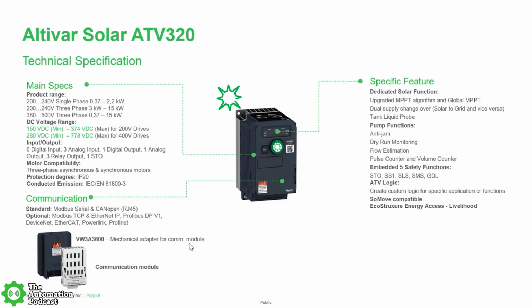Another cool thing that we have on the Altivar 320 Solar is that we also have integration into the Schneider EcoStruxure platform for remote monitoring. So for those interested in that, we can also do a deep dive later on. The MPPT is a very important thing to know anytime we're dealing with solar technology, the maximum power point tracking. In the lingo of solar, that is the specific algorithm that grabs that DC bus and creates useful power, because obviously there's going to be some ranges, some switching, some irradiation, clouds, different types of conditions that will change that DC bus. So that feature is really important to grab that changing DC bus and create useful power out into a pump, motor, fan, compressor. Very important here.